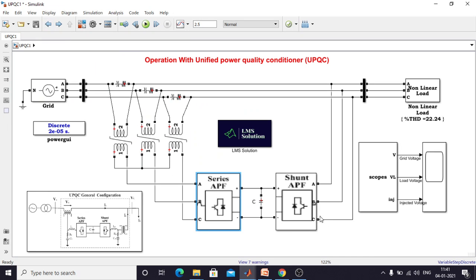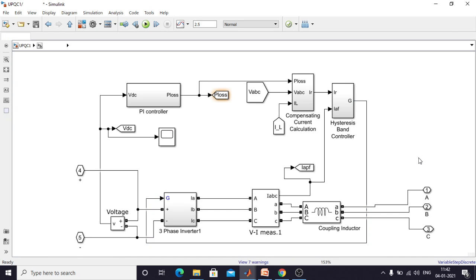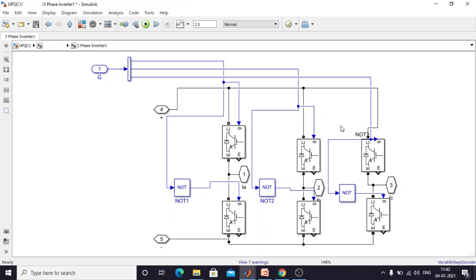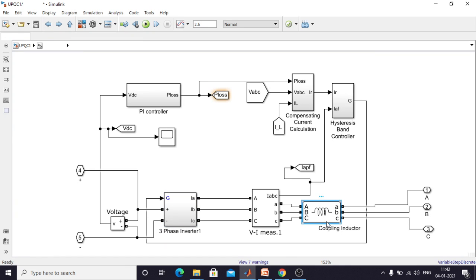Next I am going to open the shunt active filter. The shunt active filter is used to compensate reactive power in the power system, as well as improve the power quality of the source current, and also maintain the DC voltage between the series and shunt filters. This block inside the shunt active filter has an inverter connected via a coupling inductor, which acts as a current source inverter for injecting current into the power system to compensate reactive power.